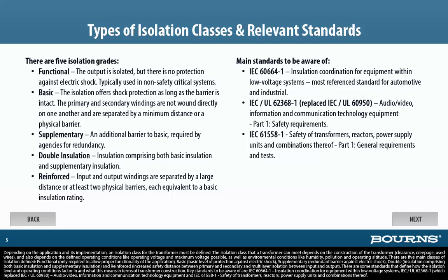There are 5 main classes of isolation defined. Functional, only required to allow proper functionality of the application. Basic level of protection against electric shock. Supplementary, redundant barrier against electric shock. Double, insulation comprising both basic insulation and supplementary insulation. And reinforced, increased safety distance between primary and secondary and multi-layer isolation between input and output.